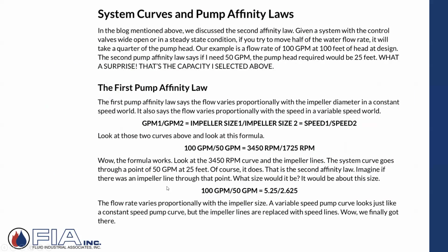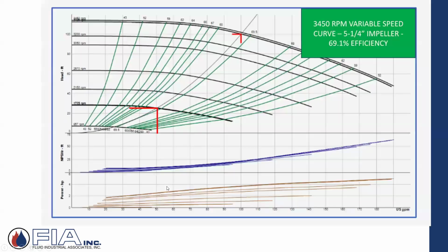And this is just a kind of verbiage. You can reference it later on when you get the copy of the PowerPoint presentation. But here what we've done is said, hey, let's go with our pump software and let's select it for variable speed. So one pump, variable speed. And really what you're doing is, instead of having a bunch of different impeller curves, on the variable speed you're looking at different speed curves, is all it is. It's describing what RPMs we're operating at. And it's really almost infinite from a max to a certain minimum. They're just highlighting a certain number of them, if you will. So within that same pump, that 3450 RPM at full speed, 100 at 100, as I vary the speed down, maybe respond to system conditions. In this case here, I would cut it.